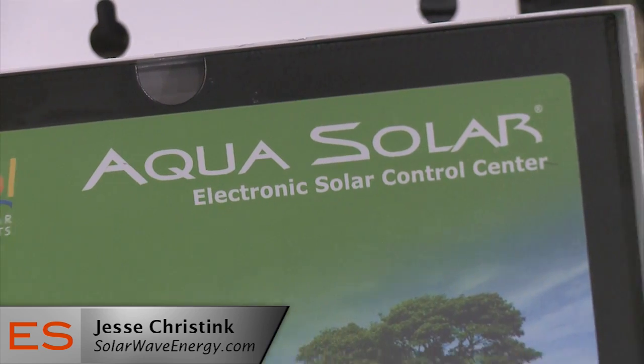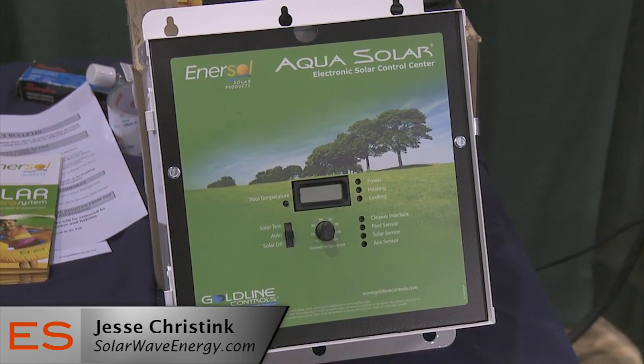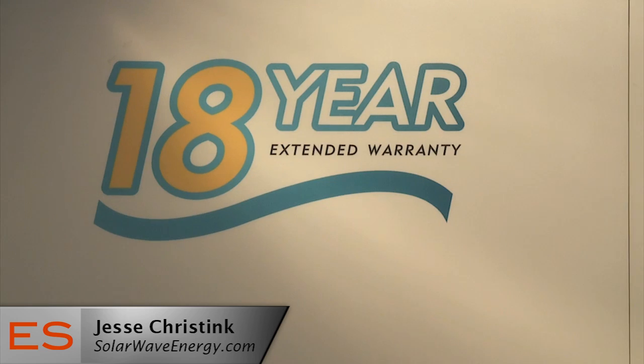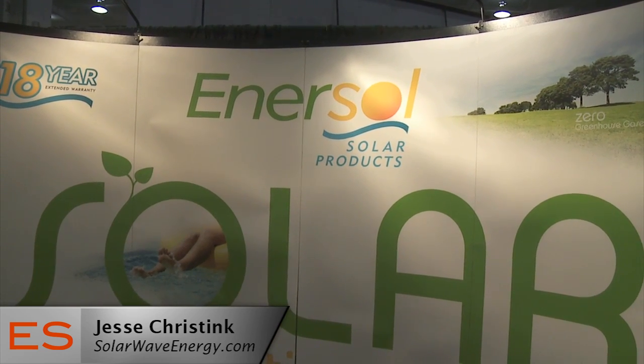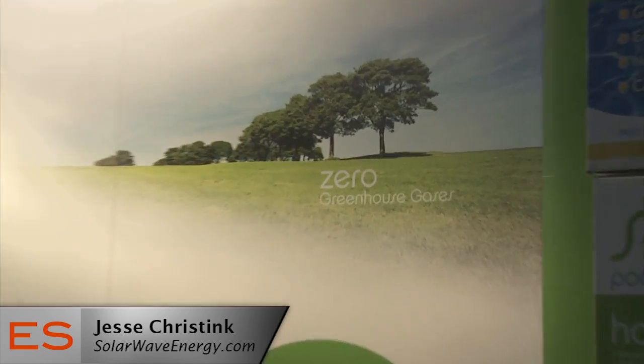that's certainly the basis. Is your system meant to be a standalone system, or is this a supplement to maybe someone who has a pool heater already? It is designed to be a standalone primary heating system, and we size it accordingly. However, in many cases, especially on new pool builds, a gas heater is already there or being built in with the pool, and we design it as a hybrid system so that they can both work together. We put in the option of setting solar as a priority so that they get all the cost savings of solar while still having the on-demand heat of a gas heater whenever they need it, and integrating them together so they can actually both run at the same time if that's ever desired.